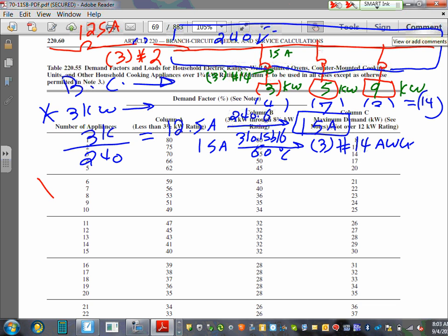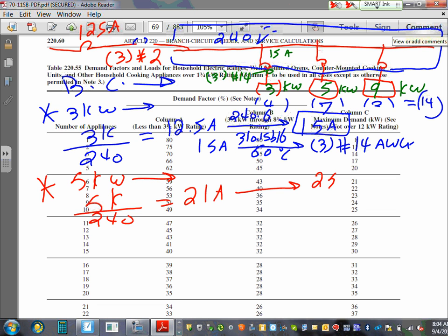The second branch circuit, my friends, what do we call it? We call it the 5 kW branch circuit. All right, so let's take the 5. Who's going to do the math? 5K divided by 240 is 20.8 amps. Okay, 21 then. And 21 amps. The same table will get you, you're going to go to the next standard, 25 amp circuit breaker, and from here for 25 amp, it's going to give you 3 conductors number.